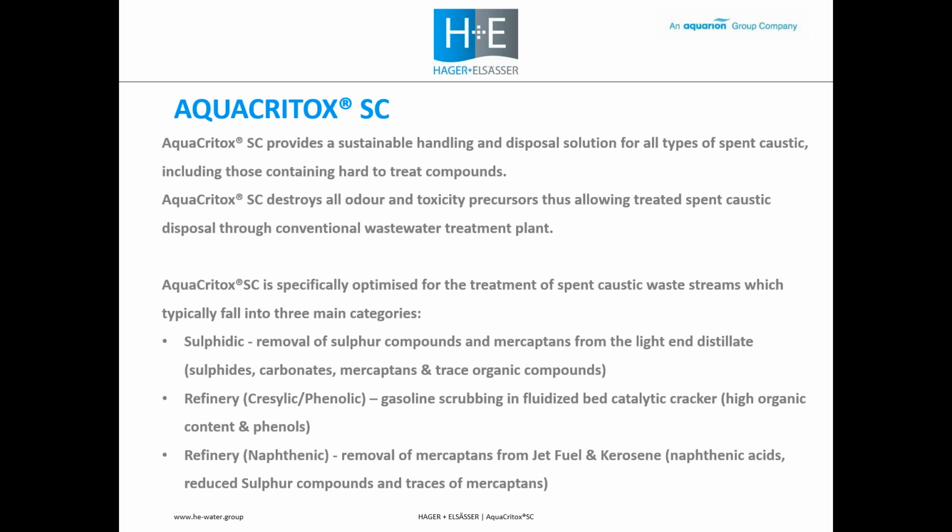We would expect typically to achieve, as said, around 100% removal of the sulfide compounds, and also for the COD itself, between 40 and 75% COD destruction of the organic compounds. These are then converted to the likes of organic acids, which can easily then be destroyed by biological treatment and other treatment downstream, if this would even be required.